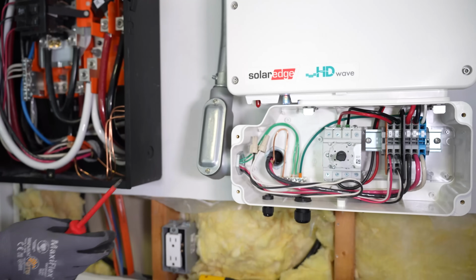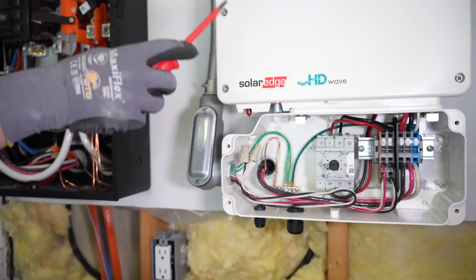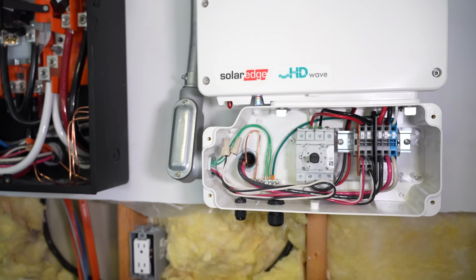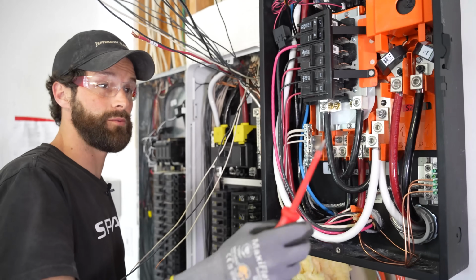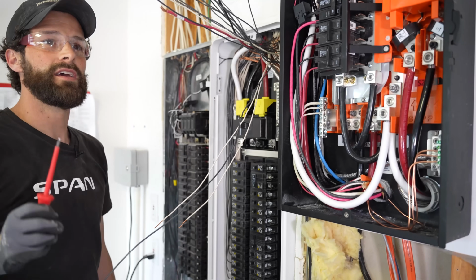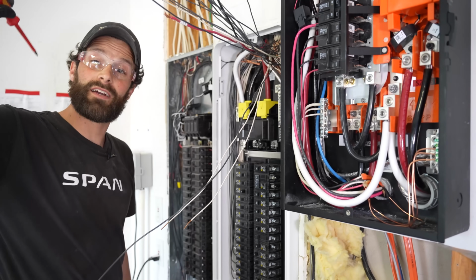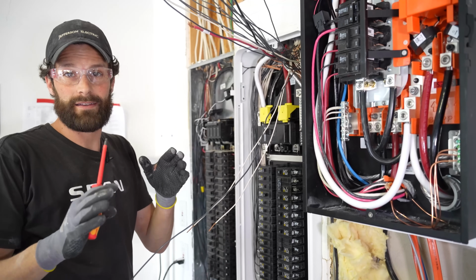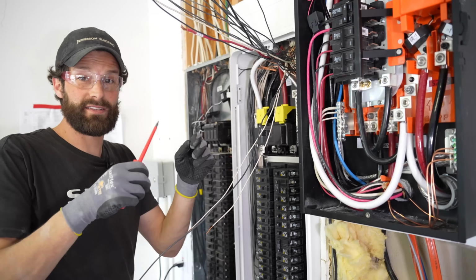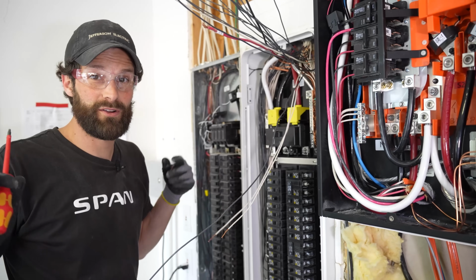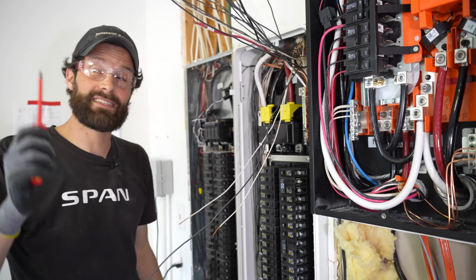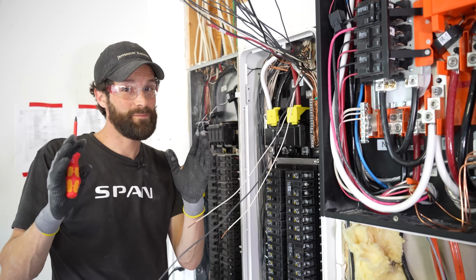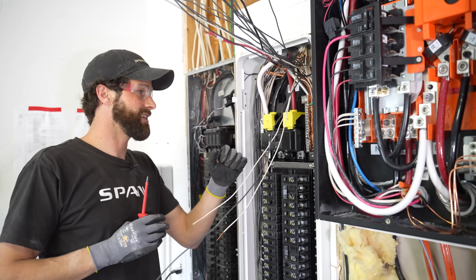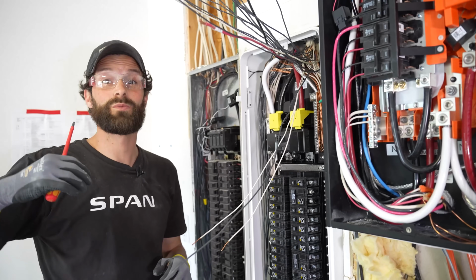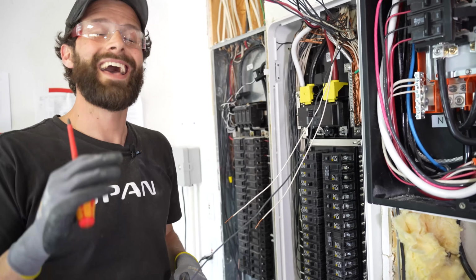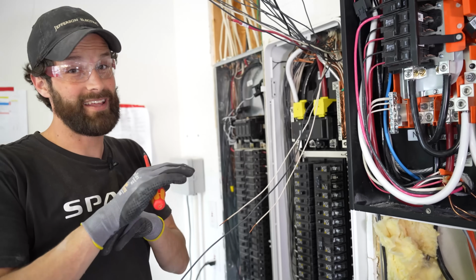SolarEdge transitioned to screenless inverters about 2 years ago. So there's an app, you scan the QR code, go through the commissioning process. It's just a pretty clean step-by-step. But when all this is done, we still have our labeling to do. PV labeling by code. Our DC conductors in the attic are labeled as DC circuits so that nobody tries to splice into them and tap off for a kitchen receptacle for a Sub-Zero refrigerator or anything cray-cray, because that DC is going to be operating at about 370 volts DC on average. Just for context, the mains in here, 240 volts, so substantially higher, blow your stuff off the shelf, in addition to being DC, not AC. It ain't gonna work, bro.